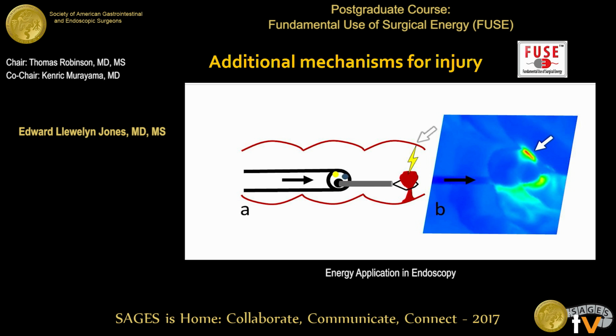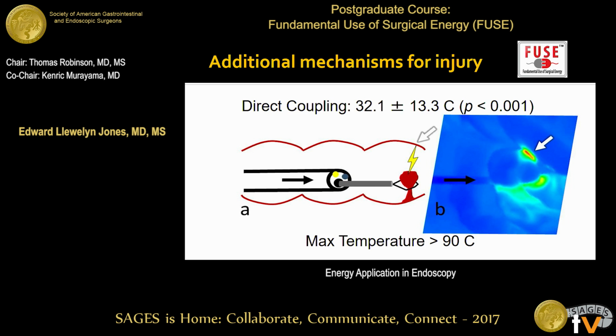And then one final mechanism during standard polypectomy, this idea of direct application: the energy can jump straight from the tip of the polyp to the opposing side of the bowel, and this can create really high energies, greater than 90 degrees Celsius. Obviously, you can create a very bad injury when you're trying to wiggle that polyp so that it'll pop off.